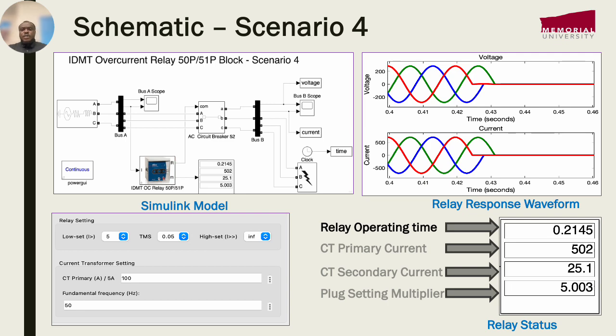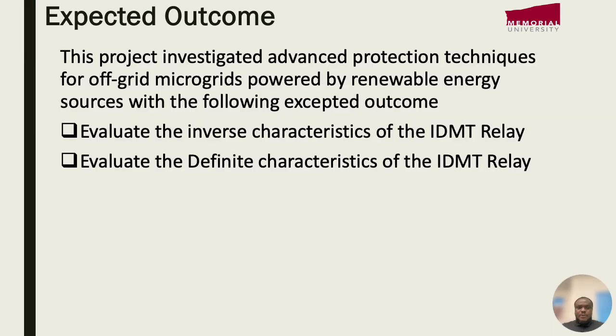So scenarios 1 to 3 evaluated and really proved the inverse characteristics of this IDMT relay, and scenario 4 evaluated and proved the definite characteristics of the IDMT relay.